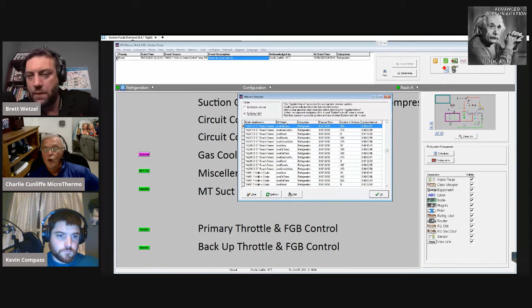I just had a comment. One of the things you can do, if you have a numerical value present about how many errors you've had, see what it is at first when you get on the job site. It's recommended that maybe you reset it and see how often the error is coming through. Monitor it for about an hour - you'll be looking over the prints and everything else trying to figure this thing out anyway. Then go back and see what it was, see what it's like after you made a repair. So if you found weird resistances when checking the Echelon cable, and you weren't getting 53 on both sides, you were getting something crazy, you fixed a certain connection, came back, reset it, and see if it's coming in and out less now to see if you actually made an impact on the network.